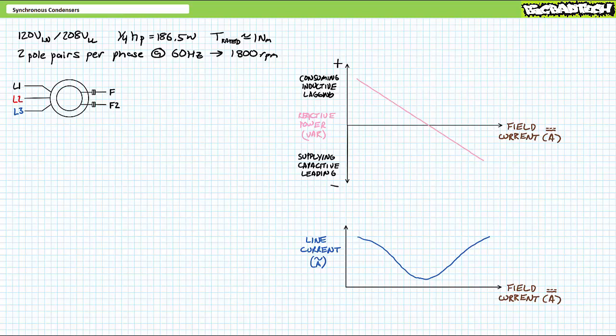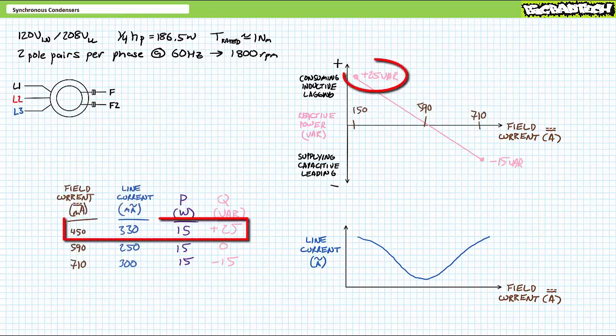First, we need to determine this particular device's upper and lower ranges of reactive power. At a minimum field excitation current of 450 mA DC, the synchronous condenser draws 330 mA of line current per phase lagging by around 60 degrees and consumes roughly 15 watts of real power to overcome friction and positive 25 VARs of reactive power. In this underexcited state, each winding appears to be inductive in nature — this is the most positive reactive power each winding would be capable of consuming.